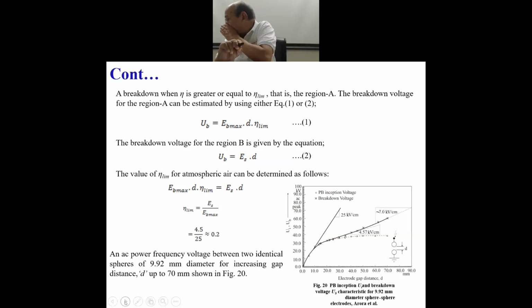This is the region A, as I mentioned. This equation gives you the breakdown voltage, and the breakdown voltage for the region B is given by the equation, that is the extent to which the streamer breakdown channels have extended. In this case, the complete breakdown will occur only when the streamer breakdown, that is partial breakdown, channels extend up to the opposite electrode, that is cover the distance of d. And the numerical value of eta limit can be estimated with these equations for atmospheric air.